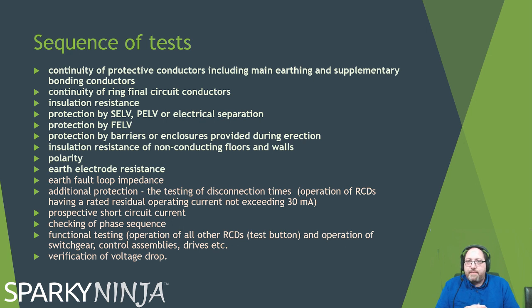You're not going to have to remember that list off the top of your head, really. If you could, that'd be great. But when you do your assessment, you'll have to carry them out in sequence, but you'll only be carrying out a few of these. You'll be carrying out continuity of protective conductors, continuity of ring, insulation resistance. That's it. Then you'll go down to polarity. SELV, PELV, FELV are if they are part of a system. Barriers during erection, again, are if required during the erection of a system. They're not going to be part of your assessment.